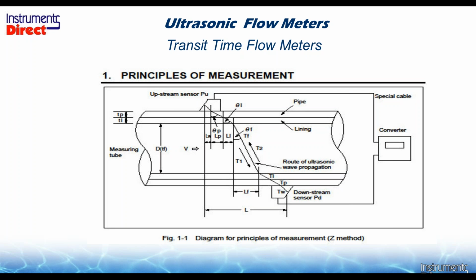Now you can see under the cover, the math behind going across the pipe, or going across the river, has a lot of calculations, which is why the earlier versions were a little difficult to work with. In this case, we've got a sensor on each side of the pipe. There's a crystal at a specific angle inside that sensor, and it needs to refract the sound into the pipe at an optimum angle. This is why you can't exchange transducers between different brands. Everybody has a different angle inside their transducer. The transducer will transmit through the pipe wall. We need to know the sound speed of that pipe, and of a liner if you have one, and then when it hits the process liquid, it refracts, and that's basically called Snell's law.